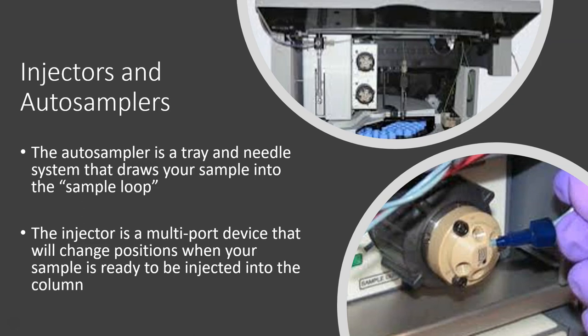The injector is a multi-port device that'll change positions when your sample is ready to be injected into the column. Normally this injector is in a position where eluent can flow through it and straight into the column. But as soon as your sample is in the sample loop and ready to be injected, this port will open up for your sample to go into the column, inject the sample, and then it'll go right back to eluent so that eluent can continue flowing through the system.